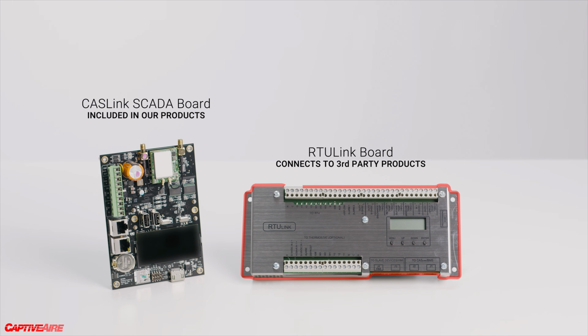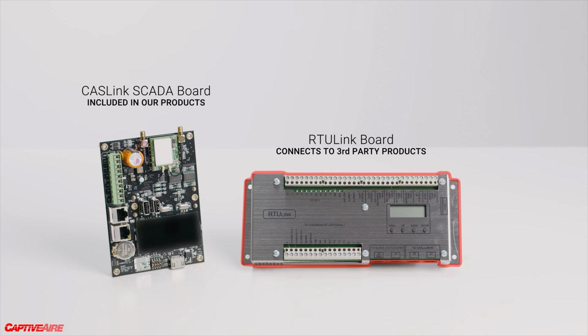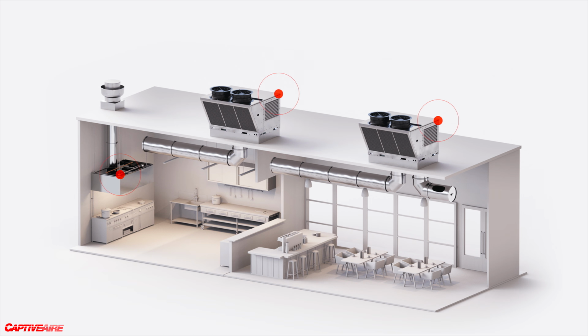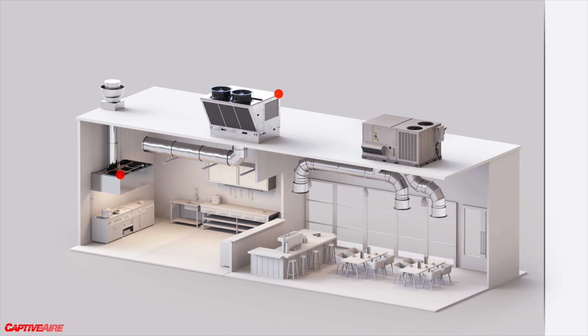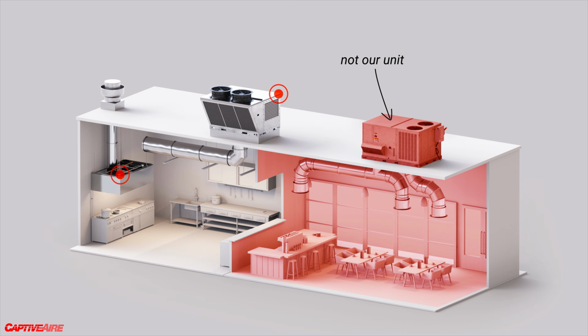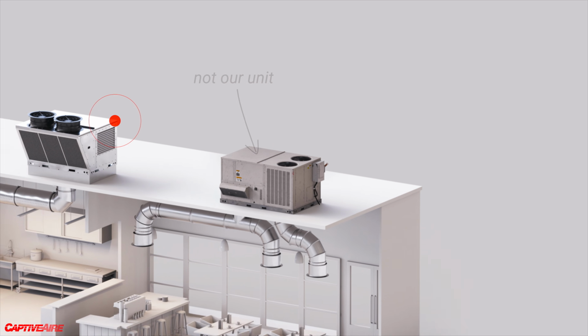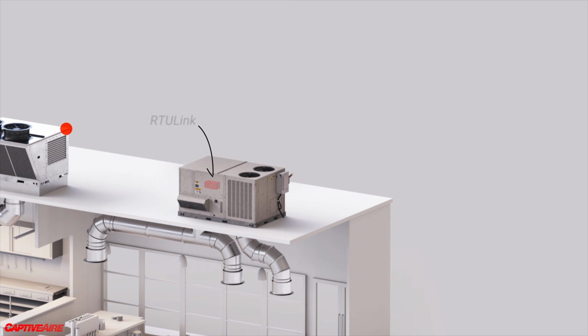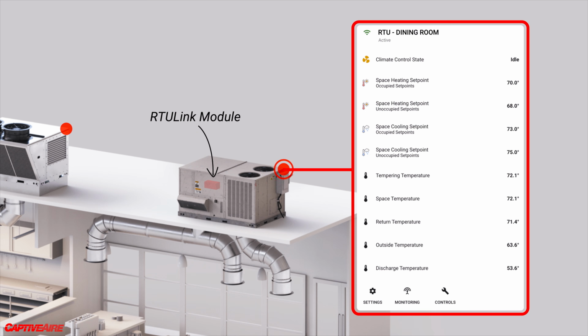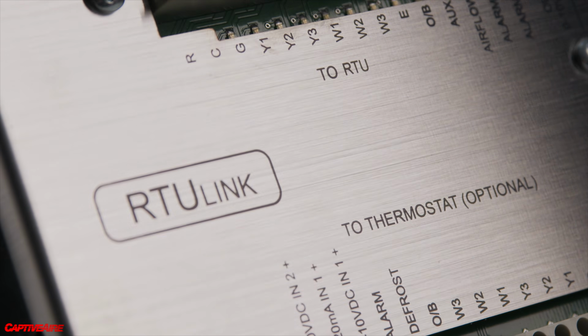RTU-Link is another product offering. This is a control board that's meant to actually interface with somebody else's rooftop units. Sometimes you might have, say, a restaurant where you have a Paragon serving the kitchen space, but then we've got somebody else's rooftop unit serving the front of house. And if this comes up, we want to try to have as much equipment under our monitoring view as possible so that we have the best holistic view of the building and how it's operating. We're talking a couple hundred dollars to have a small control board installed in that equipment.